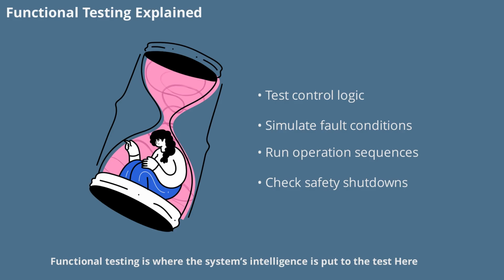Functional testing is where the system's intelligence is put to the test. Here, we check control logic, alarms, and time schedules. Normal and fault conditions are simulated to see how the system responds. For example, we might run an air handling unit startup sequence or test safety shutdowns and interlocks. This stage confirms that the BMS can handle real-world scenarios reliably.